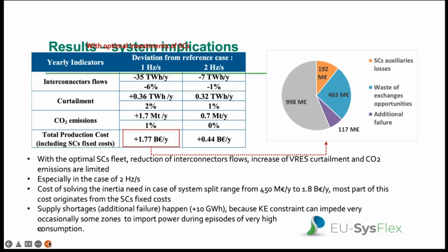We can see that in the 1 Hz per second case, we have a slight decrease of interconnector flows, minus 6%. Because we cannot export as much as before, we sometimes have to curtail renewable production, plus 2%, which generates some additional CO2 emissions, plus 1%. Globally, the total production cost increases by around 2 billion euros a year. Half of this amount relates to the fixed cost of synchronous condensers, 10% of that amount is for synchronous condenser losses, and a quarter of this amount is because of less optimal use of the interconnectors.